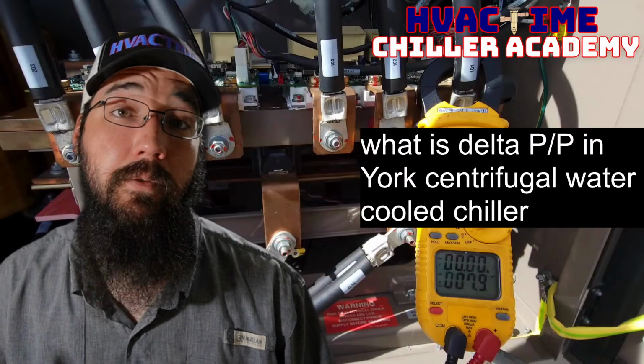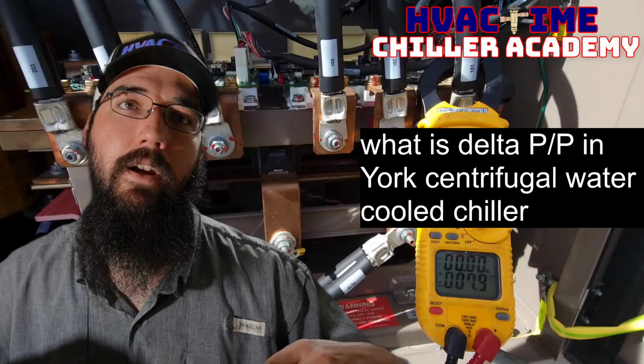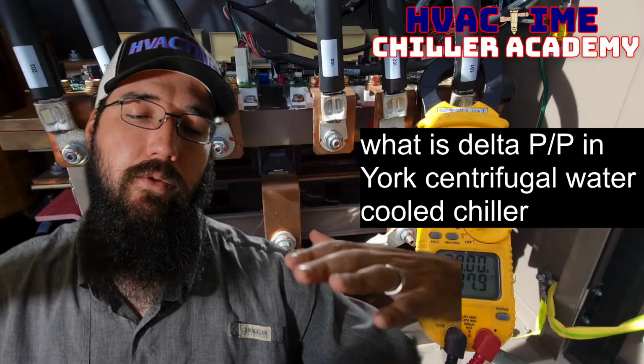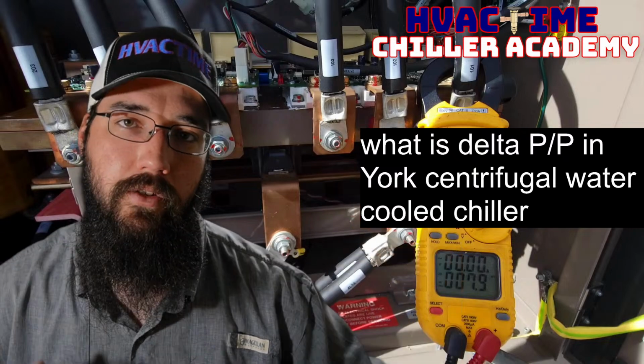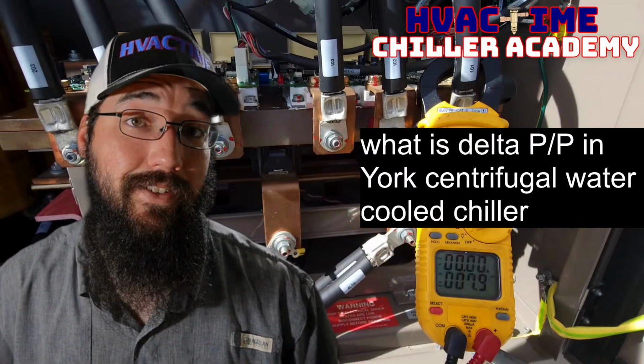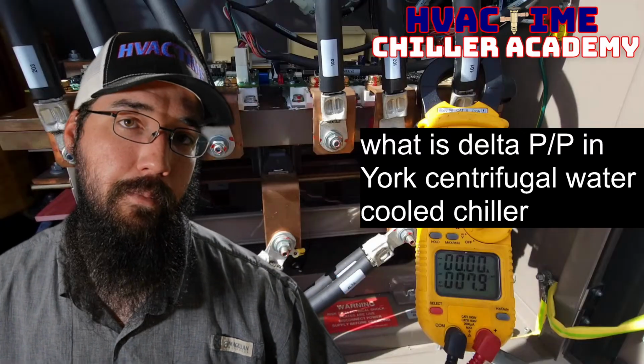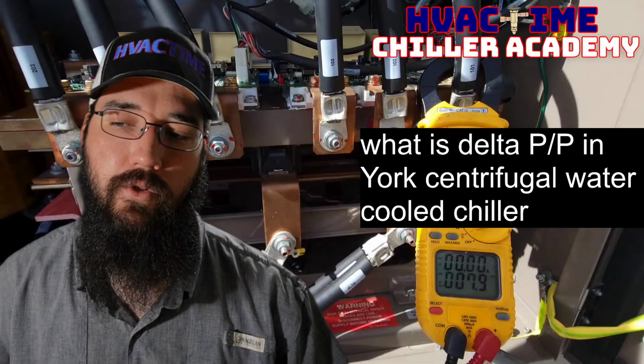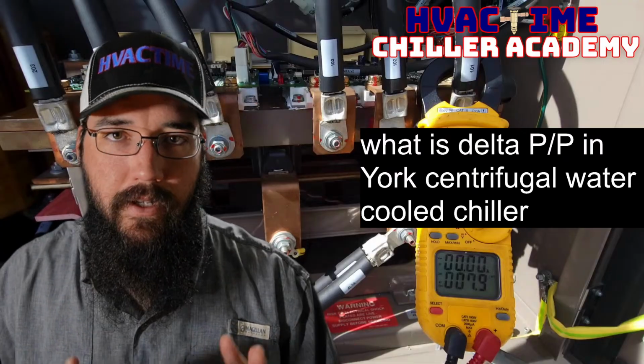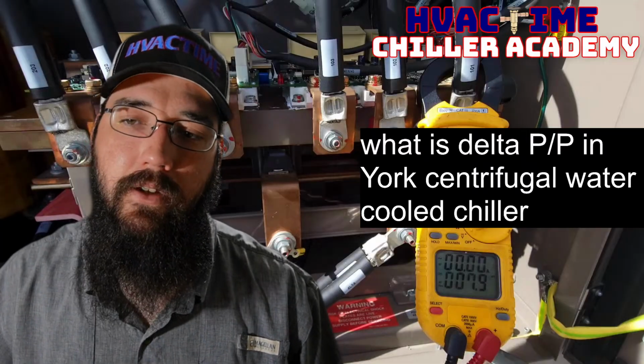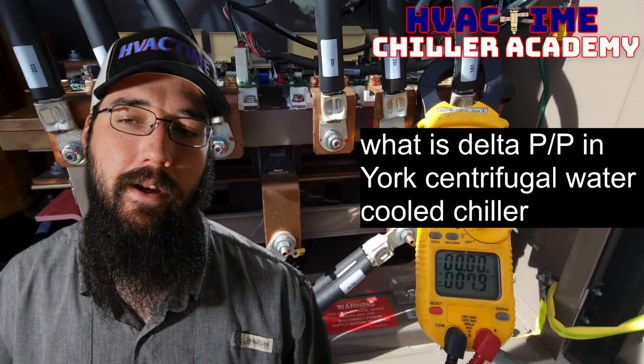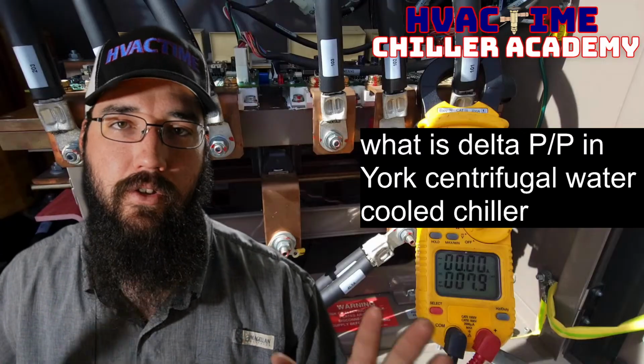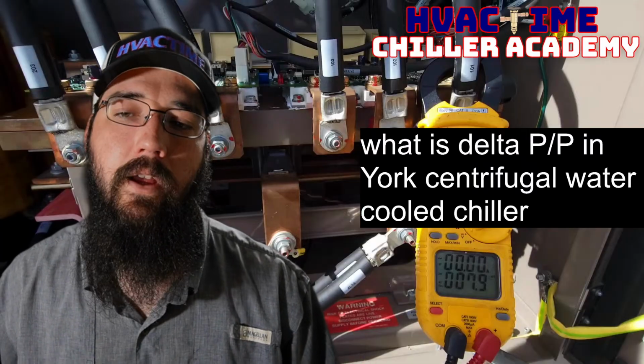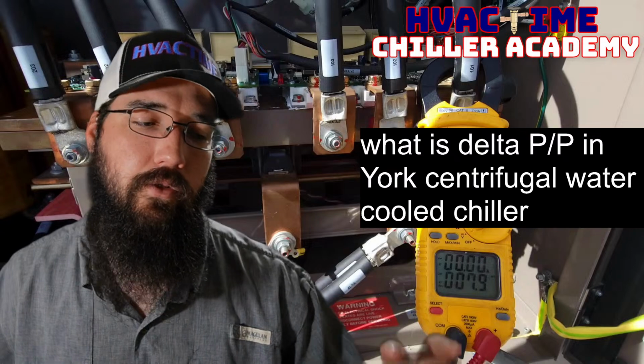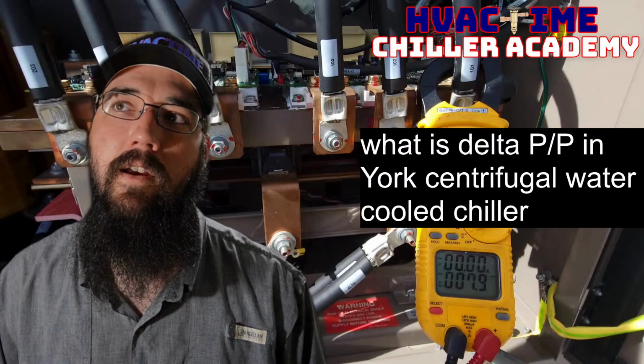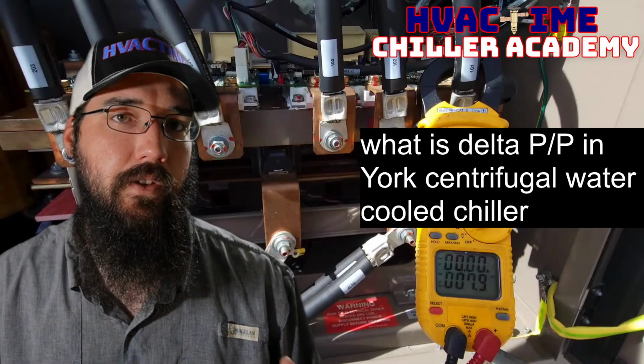So that is a symptom the surge map can create, where we're staying at a high speed that's keeping us partially loaded, whereas if we could slow the motor down with the drive, then we could unload it significantly and we could still maintain operation with that low load condition. So that's just, yeah, this is an example of how that surge map is working, what delta P is being used for inside of that YK panel. And yeah, it's a form of expressing compression ratio, which is just another way to say lift. Okay, so compression ratio and lift, these things are different forms of saying something similar, and we use them in different ways.